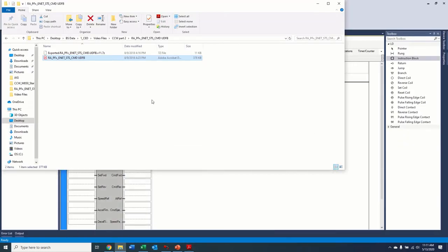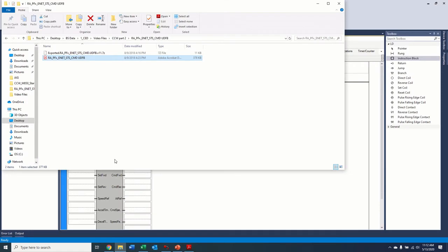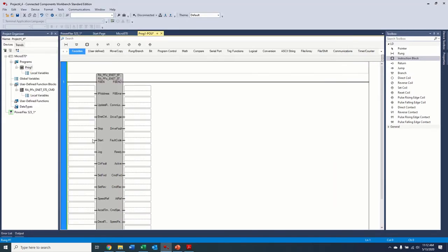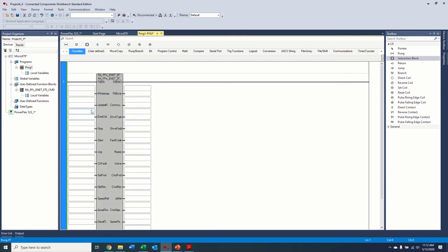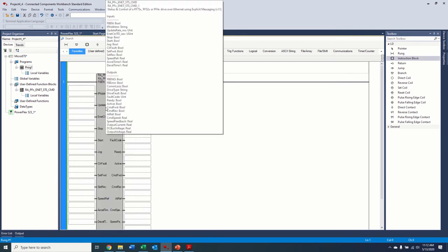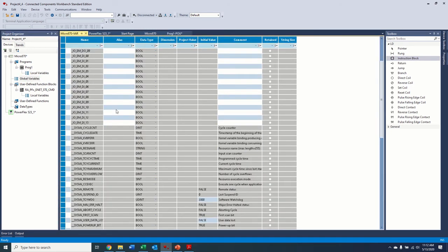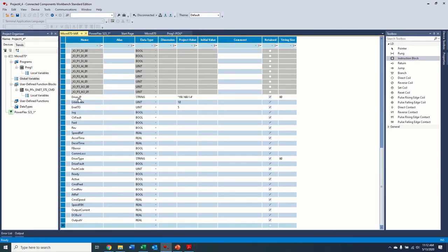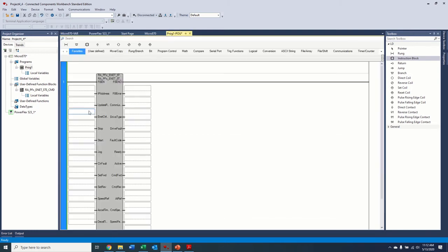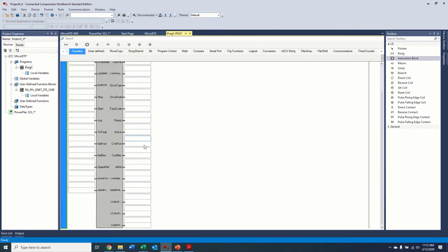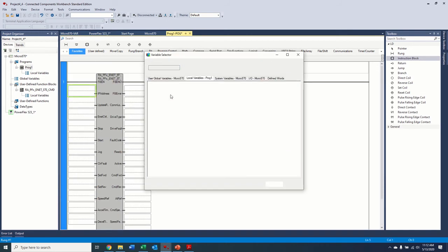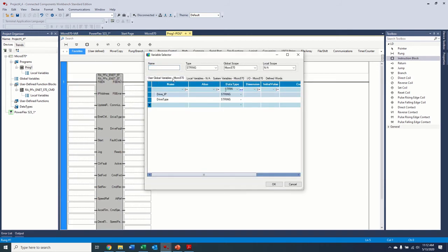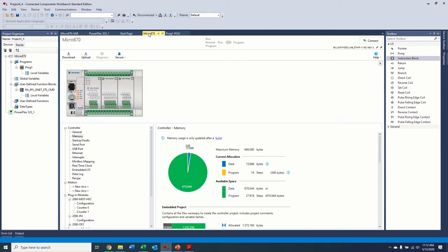So we're going to minimize that. And it also, back at the bottom, it tells you what you have to set to allow the drive to accept the Ethernet command. So back over here, you would want to create a lot of tags to do this. I've already done that to save time. I've created a lot of tags under our global variables. You can see I have my drive IP, update rate and things like that already created. But what I wanted to show you first is the only thing you need to do to get information out of that drive is to put the drive IP address in. So if you don't even want to control the drive, you just want to know all of the outputs, we can do that by simply putting in here our global variables and our drive IP. We'll put that in there. We're going to save and come back over and download to our controller. I just want to show you this first.